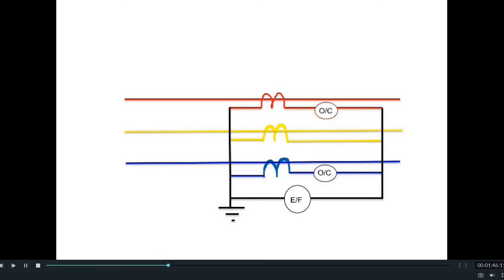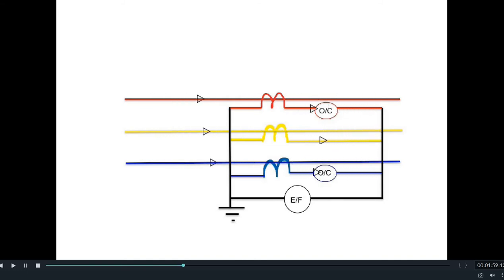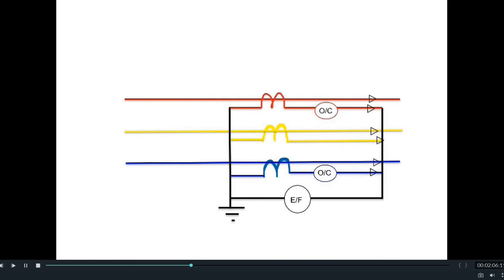We will see how two overcurrent relays and one earth fault relay in combination fully protect the transmission line from any kind of fault. In normal condition, when normal currents are flowing through the transmission line, normal currents also flow through the CT secondary in balanced condition — the vector combination of R, Y, and B phases will be almost zero, so there will be no current flowing through the earth fault relay and the transmission line will work properly.